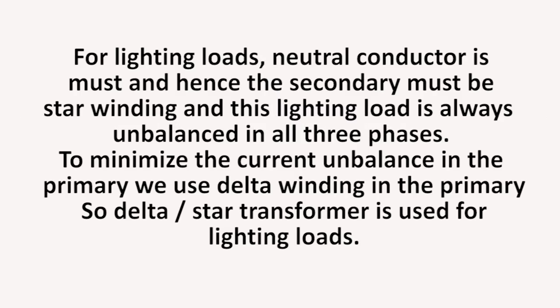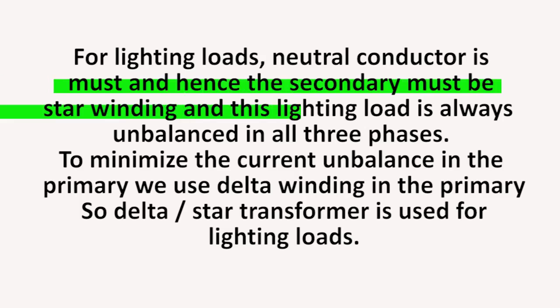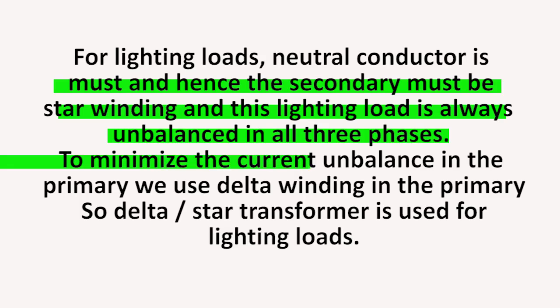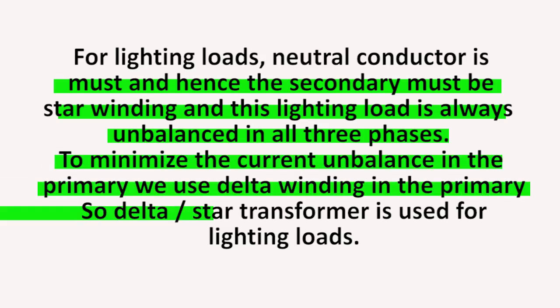For lighting loads, neutral conductor is a must and hence the secondary must be star winding, and this lighting load is always unbalanced in all three phases. To minimize the current unbalance in the primary, we use delta winding in the primary. So, delta star transformer is used for lighting loads.